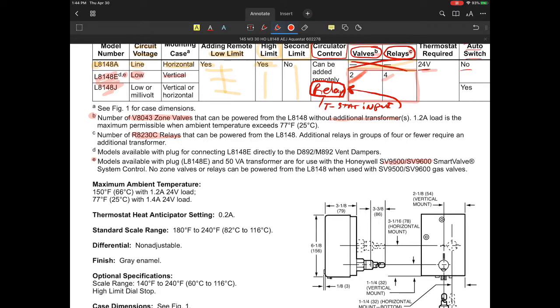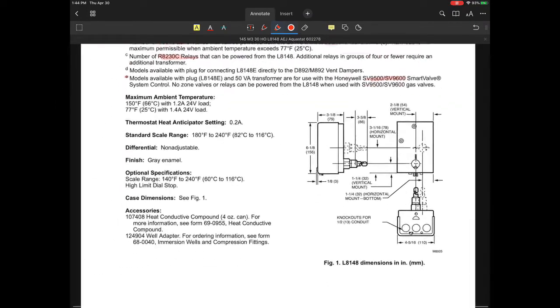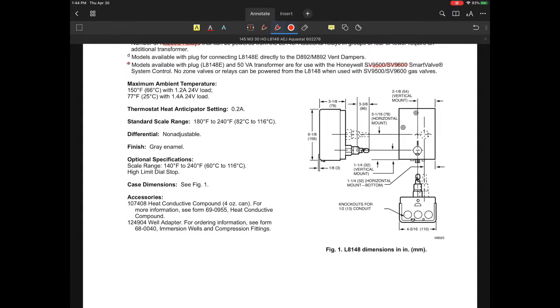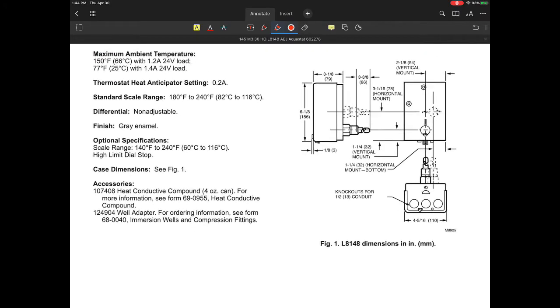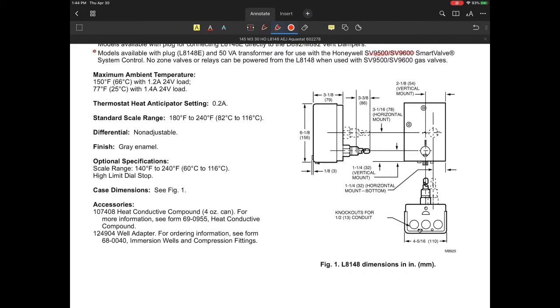Those smart valve control systems, you have to be a little bit careful. If you are going to be doing that, they're specifically telling you don't power the zone valves if you have a system that has a smart valve on there. It would be better to not do that. I would much rather see us use a zone valve control system, a zoning control board, from a diagnostic standpoint. I think that makes the most sense. All right.